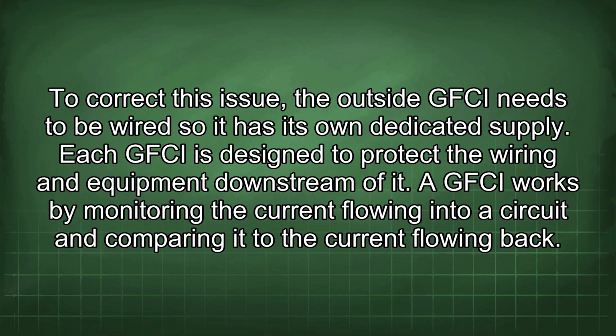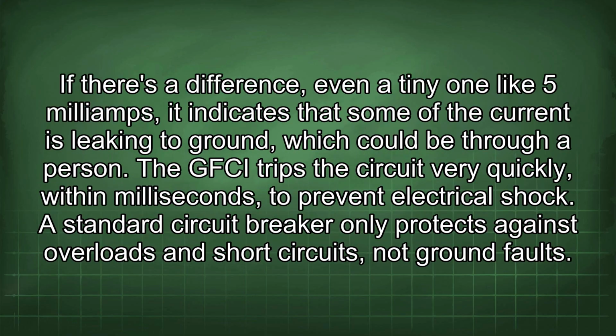To correct this issue, the outside GFCI needs to be wired so it has its own dedicated supply. Each GFCI is designed to protect the wiring and equipment downstream of it. A GFCI works by monitoring the current flowing into a circuit and comparing it to the current flowing back. If there is a difference, even a tiny one like 5 mA, it indicates that some of the current is leaking to ground, which could be through a person. The GFCI trips the circuit very quickly, within milliseconds, to prevent electrical shock.